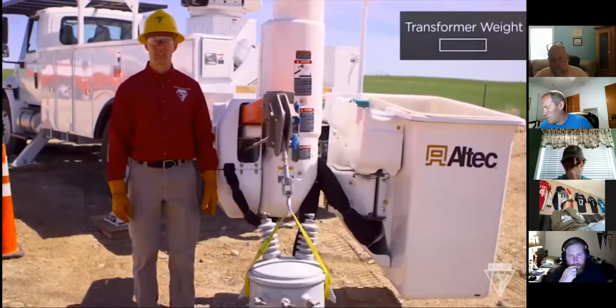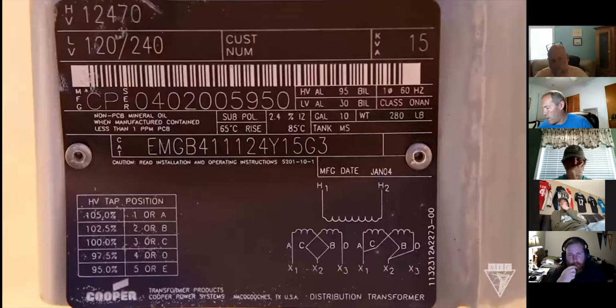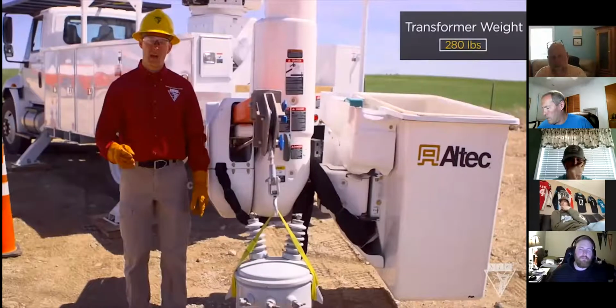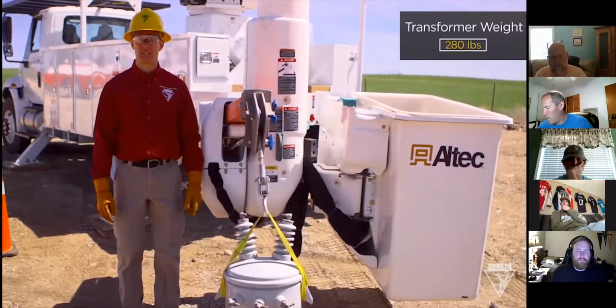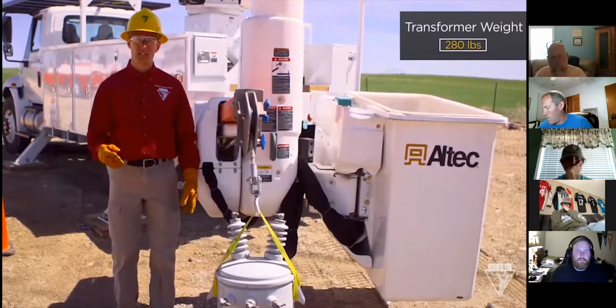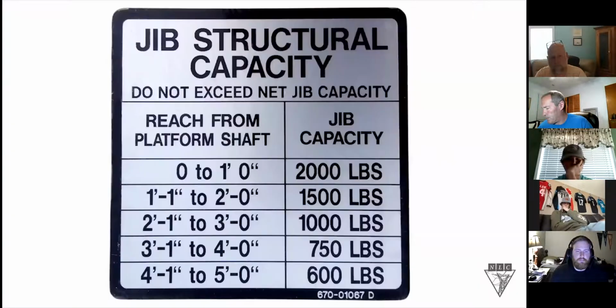So here I'm set up to lift this transformer. I looked at the nameplate, so I know it weighs 280 pounds. Now I have to make sure I can pick it up safely. This Altec truck has a jib capacity placard on the top side of the jib. Here I can find the max weight that can be lifted at different extensions.